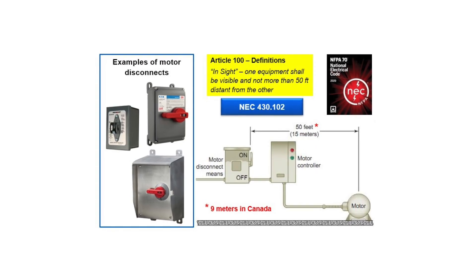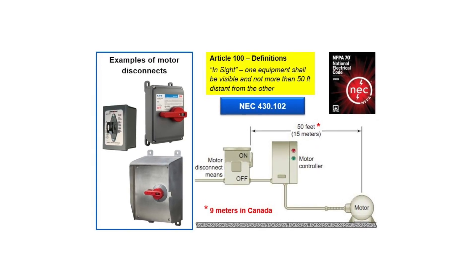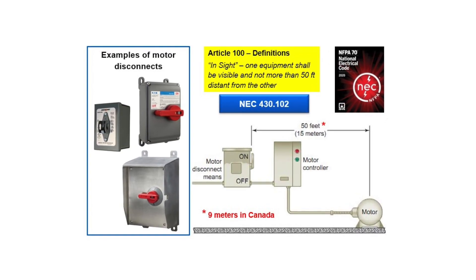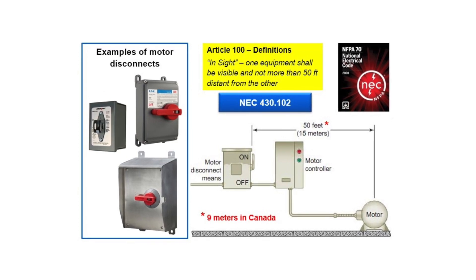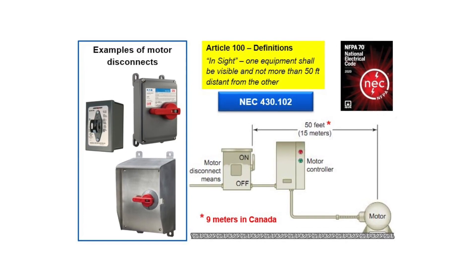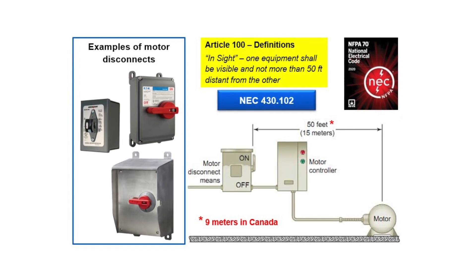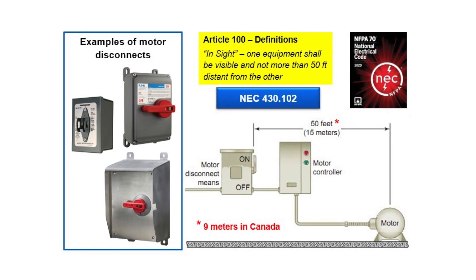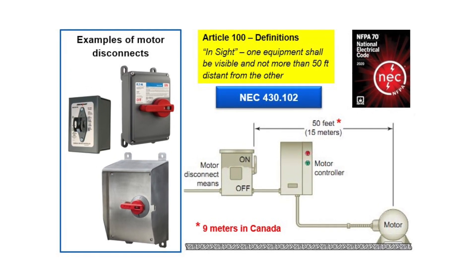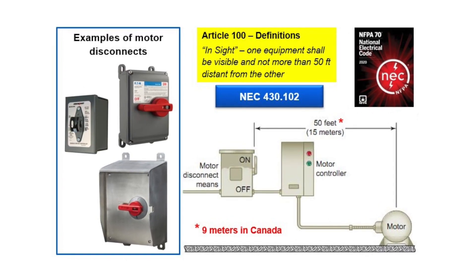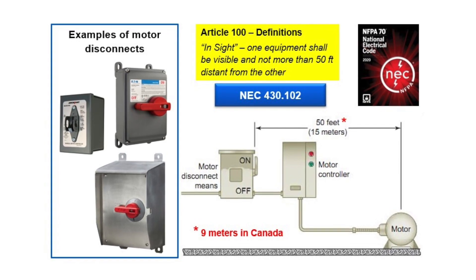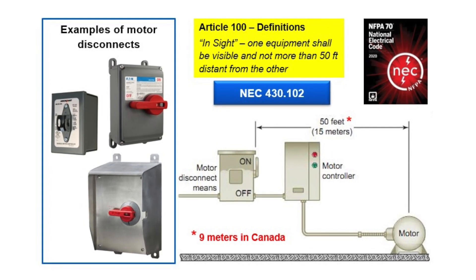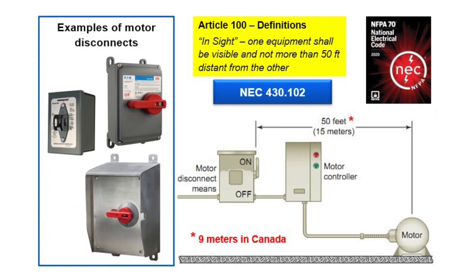There's one more important requirement for these devices, and it deals with location. In general, the disconnecting means must be in sight of either the motor controller or the motor itself. The term 'in sight' means the two pieces of equipment must be clearly visible from each other's location and no more than 50 feet apart. This is to ensure a lockout/tagout provision is readily available for safety. Note that in Canada, this in-sight distance is only 9 meters, which is a little less than 30 feet.